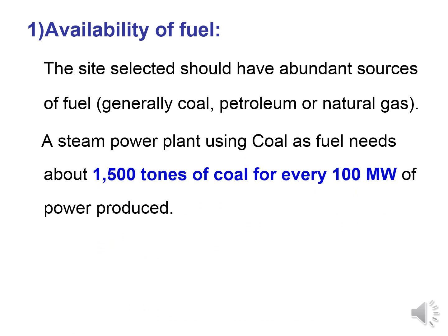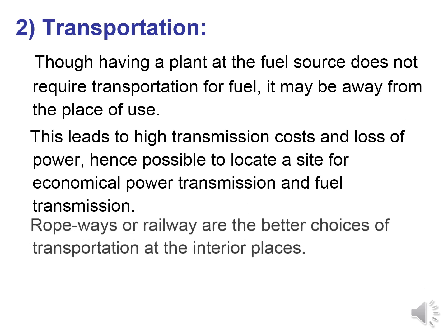Fuel availability should be large. A steam power plant using coal as a fuel needs about 1500 tons of coal for every 100 megawatt of power produced. So for 200 megawatt, we require 3000 tons of coal. Generally we can use coal, petroleum, or natural gas as fuel. This availability must be met for production of steam power.